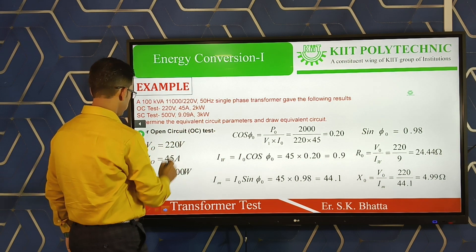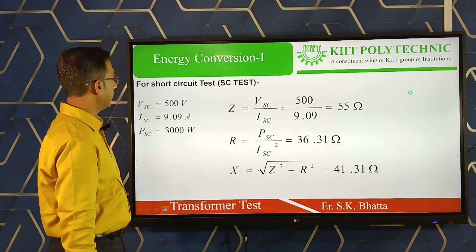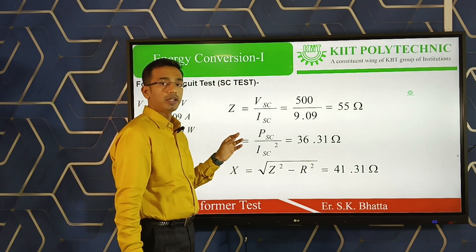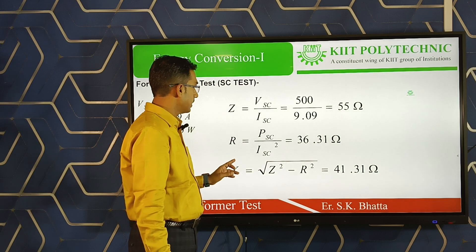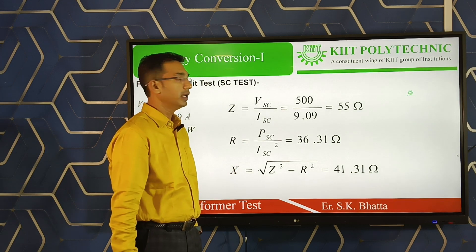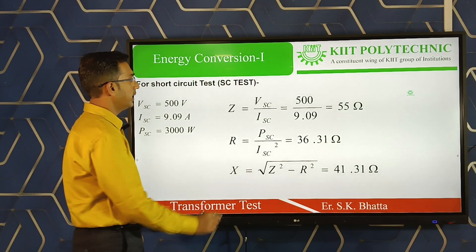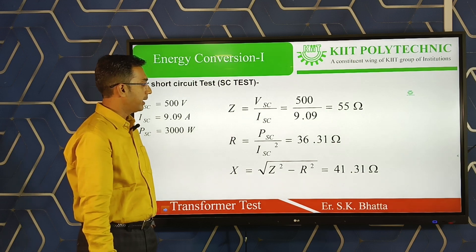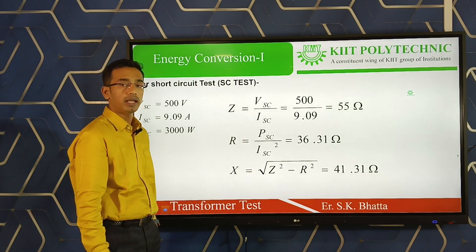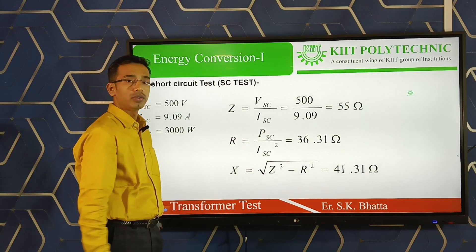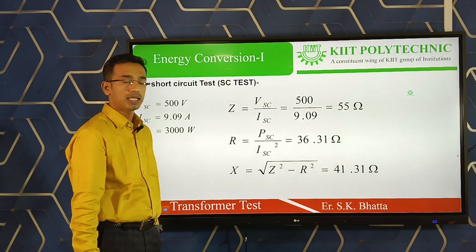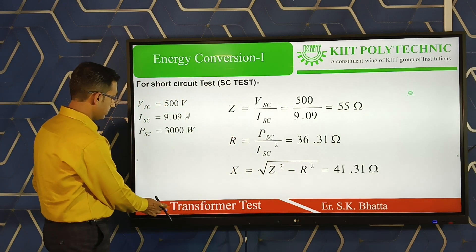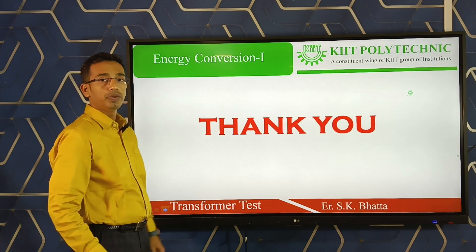From the short circuit test, voltage Vsc = 500 V, current Isc = 9.09 A, and power Wsc is given. The equivalent impedance Zeq = Vsc / Isc = 500 / 9.09 = 55 Ω. The equivalent resistance Req = Wsc / Isc² = 36.31 Ω. The equivalent reactance Xeq = √(Zeq² − Req²) = 41.31 Ω. This completes the example. Hope you understand — thank you.